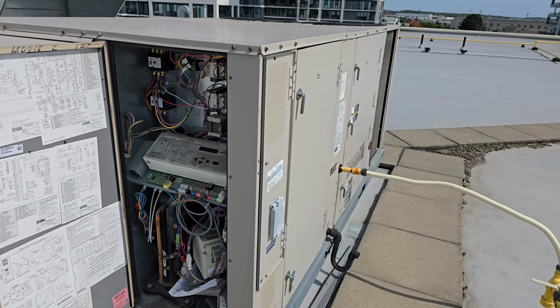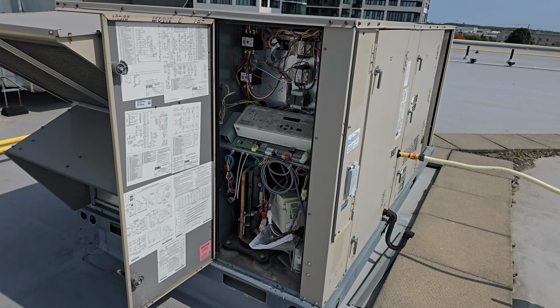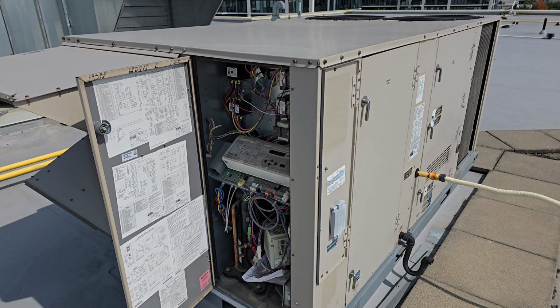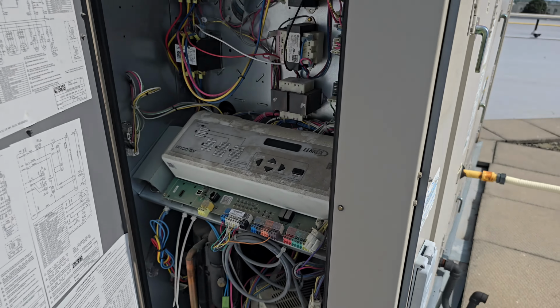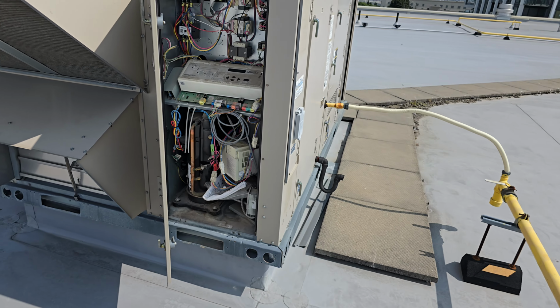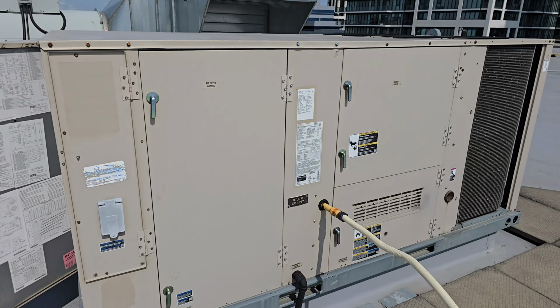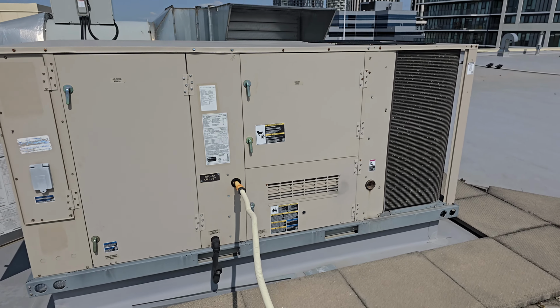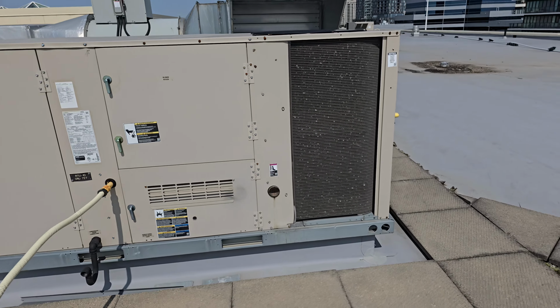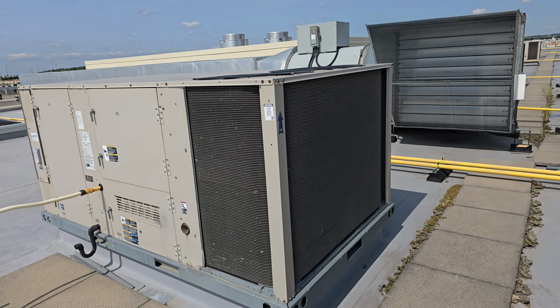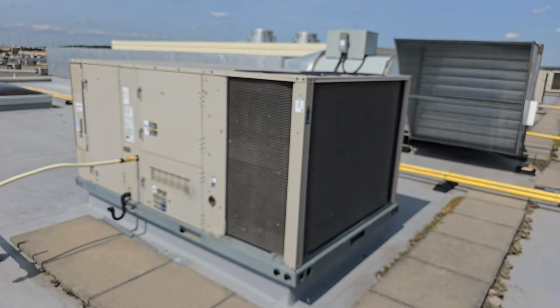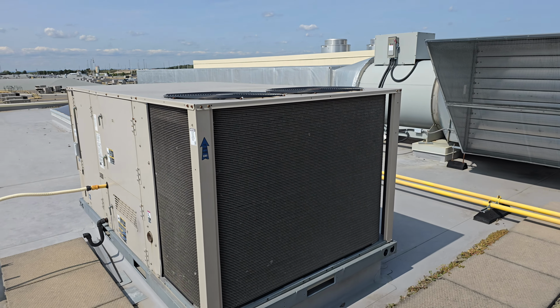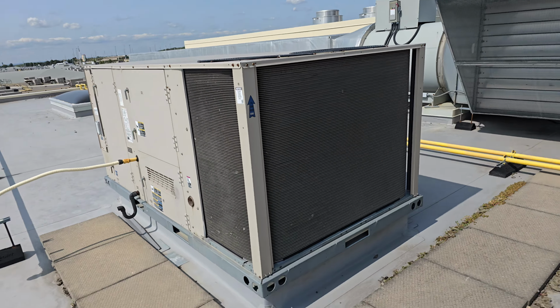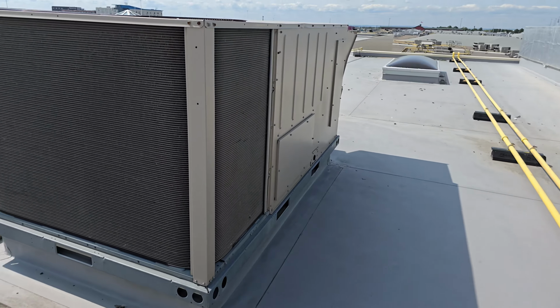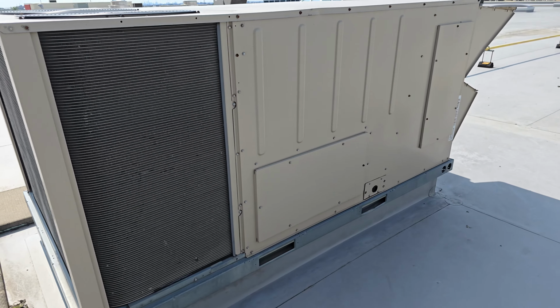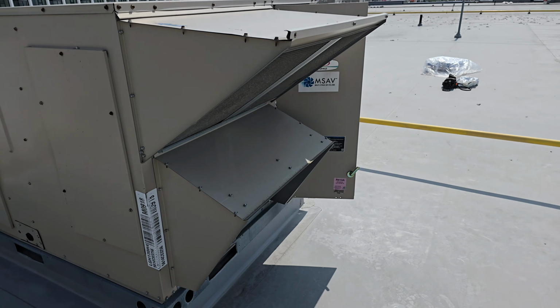Usually when I come in for any preventive maintenance, I always want to see the state of the present equipment. If it's on heating, I want to fire the heating and see if it's working, and then fire the cooling section to make sure it's okay too. The reason I do that is sometimes you come in, don't check it first, and just start doing the preventive maintenance. The owner might tell you the heating and cooling was working, but after the service is done, there's no cooling even though the heating is okay. So it's better to try both, see that they're working, and report to the owner whether the heating is working, the cooling is not working, or vice versa, or both are working.